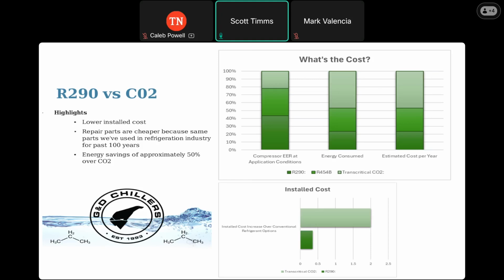So for that reason, repair is cheaper, and then also the repair parts are quite a bit cheaper as well because they are just readily available in the market since there's really nothing different there. And like I said, whenever CO2 moves to transcritical, you lose about 50% of the capacity. So in Tennessee, obviously it gets pretty warm in the summer. You're above 82 degrees outside a fair amount of the year. So you're gonna be running into those issues a fair amount of the year. On to the next slide.